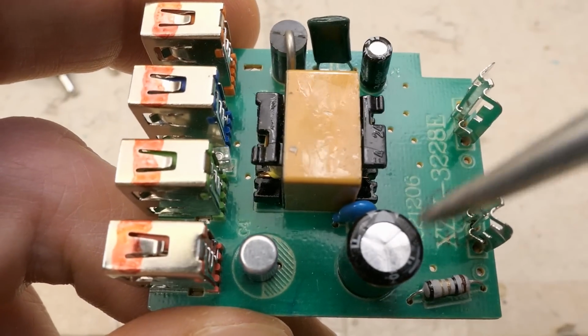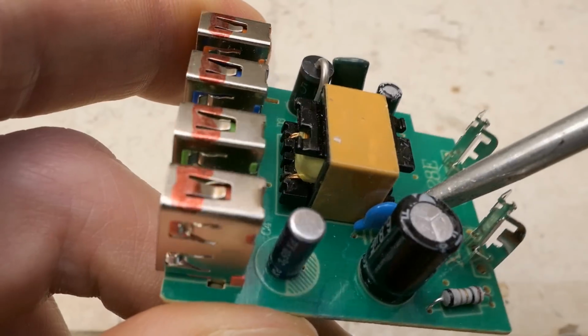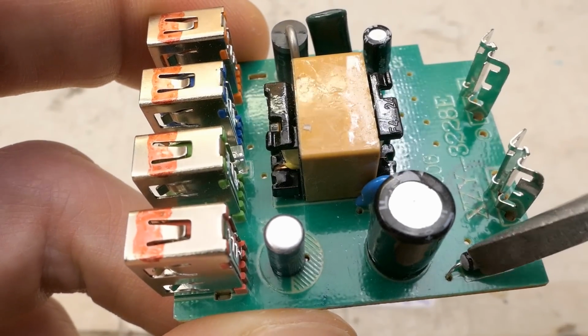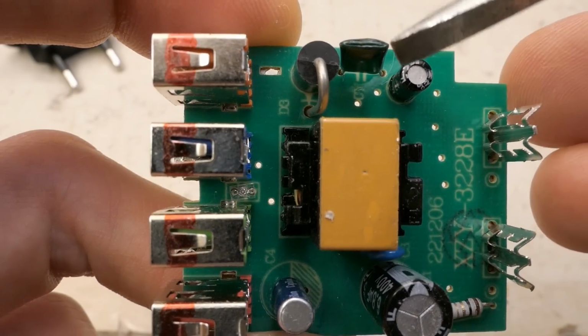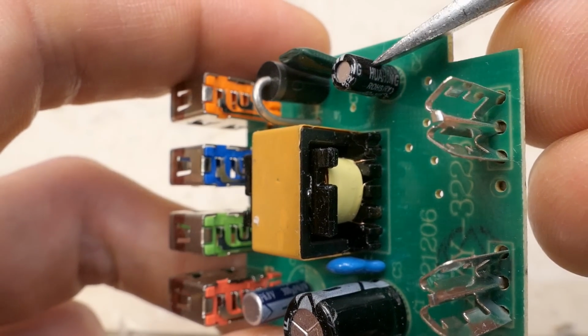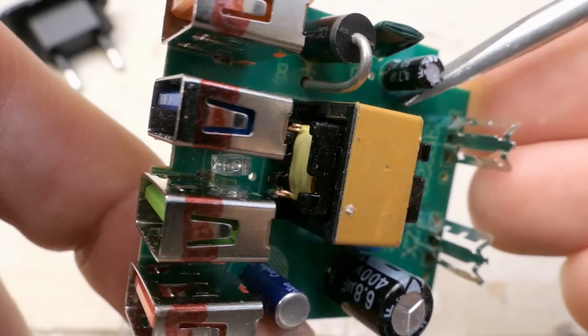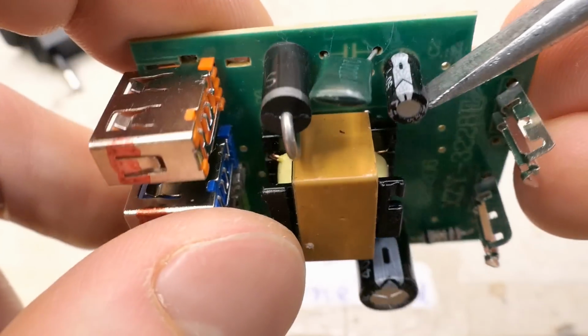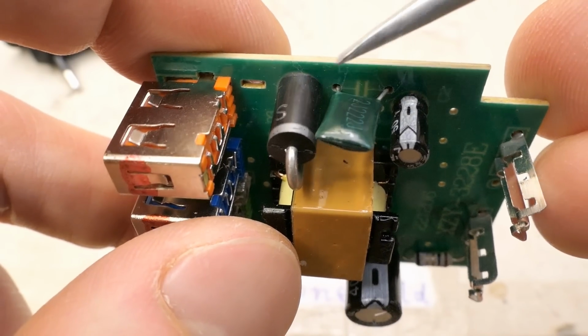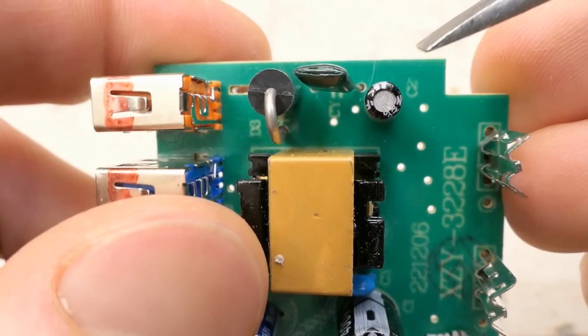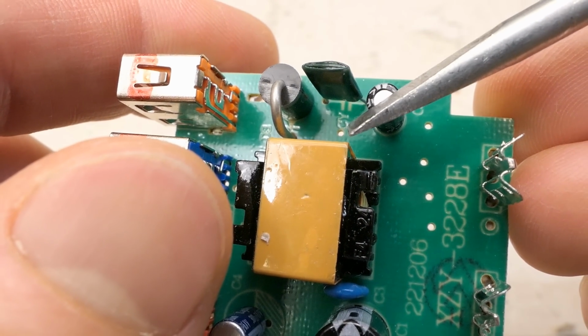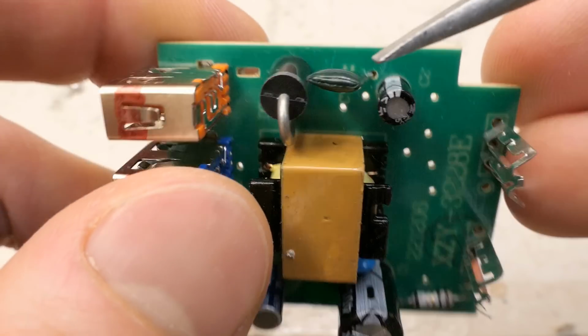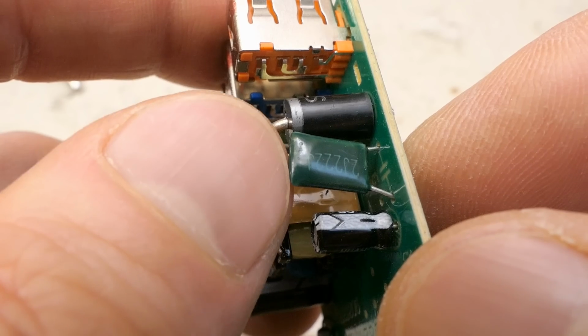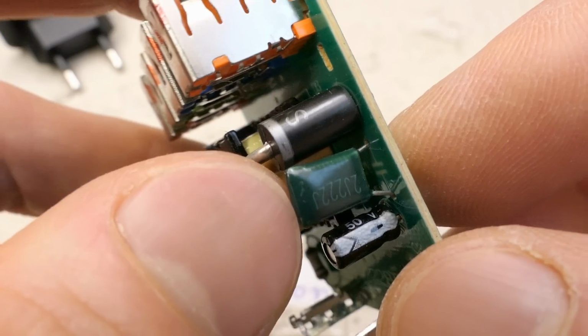And here is the capacitor in the snubber network, the small blue one here. The inrush resistor may be fusible, and the small capacitor rectifying, or smoothing, the auxiliary winding. And here is the capacitor between the primary and secondary side, which is again not a safety capacitor. The board says CY, a Y-class capacitor, but it's not. I have never seen this between the primary and secondary side.